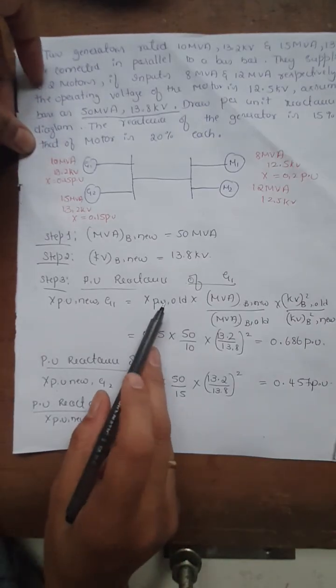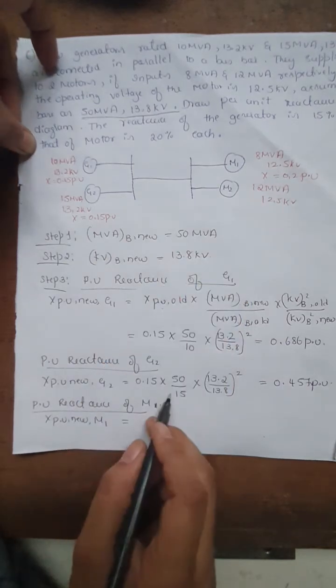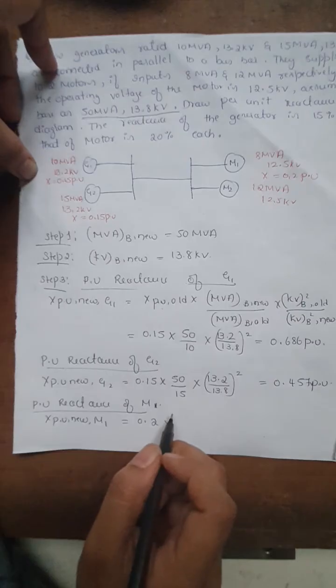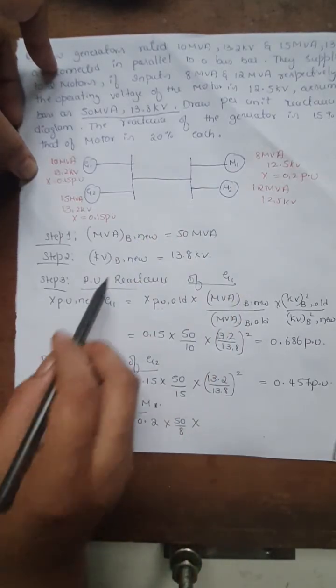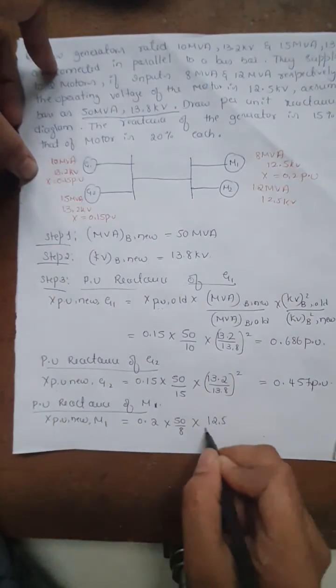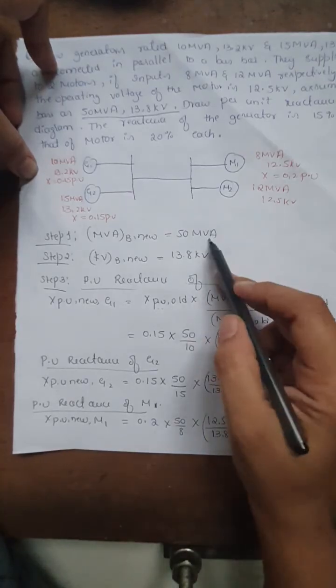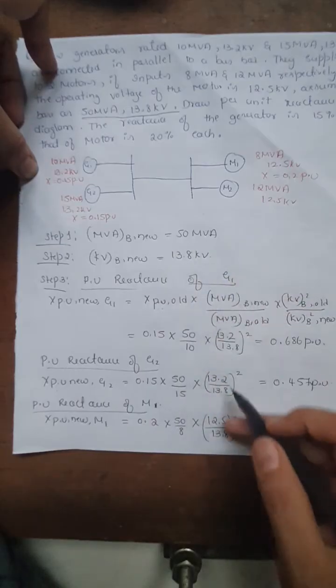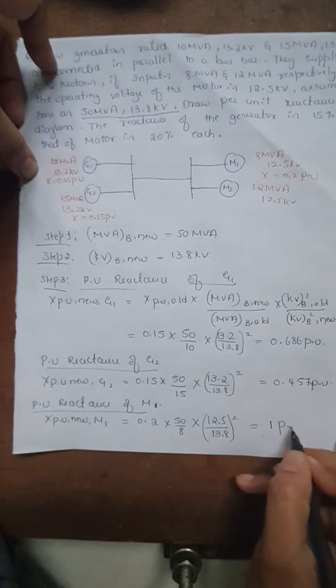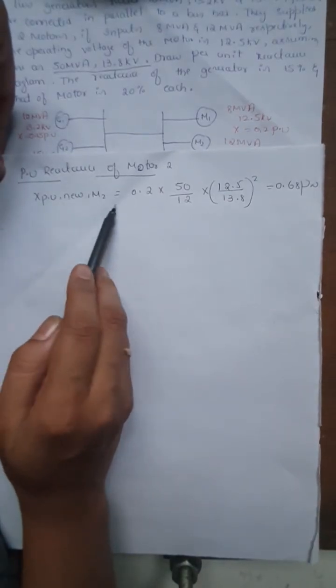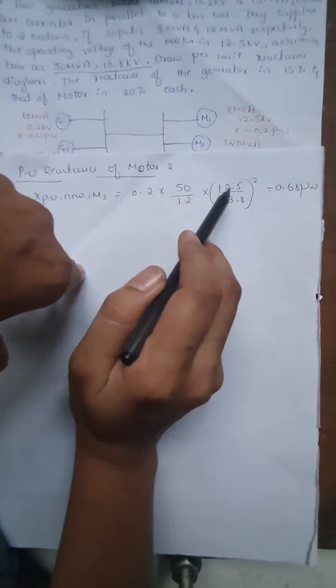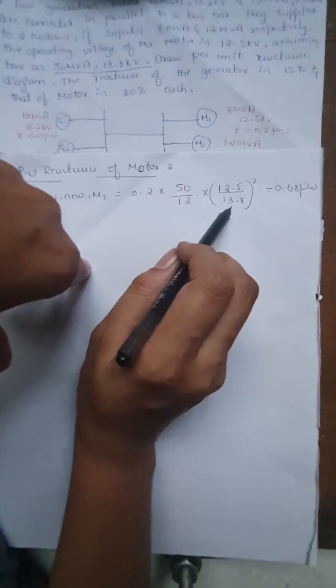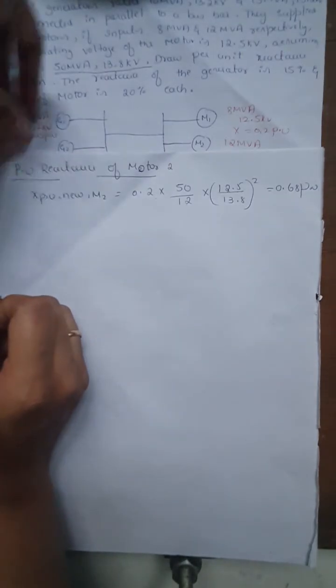For motor 1, using the same formula: X(pu, new) = 0.2 × (50 / 8) × (12.5 / 13.8)² = 1.0 per unit. The old kV base is 12.5 kV and the new base voltage is 13.8 kV, which is the common base for all components. For motor 2: X(pu, new) = 0.2 × (50 / 12) × (12.5 / 13.8)², with old MVA = 12 MVA and old kV = 12.5 kV, new kV = 13.8 kV.